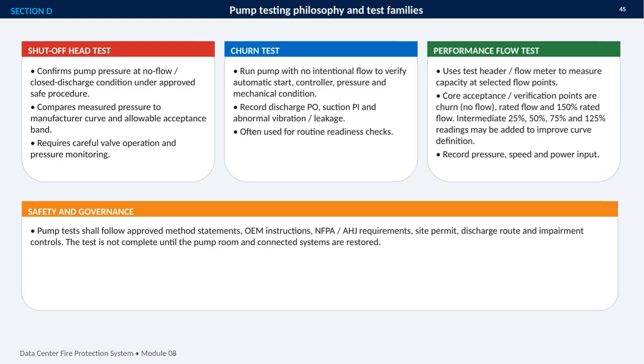This section introduces the main pump testing philosophy and the test families used to verify fire pump readiness. The first is the shutoff head test, which checks pressure under a no-flow, closed discharge condition. The measured result is compared with the manufacturer's pump curve and the approved acceptance range, with careful valve operation and continuous pressure monitoring. The churn test also operates the pump without intentional flow, but its focus is broader, confirming automatic start, controller response, pressure behavior, and overall mechanical condition.